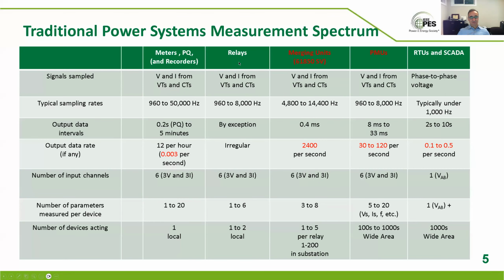Then we get to our more standard digital relays and meters. They sample at the rate internally they need. In a way, they are the front end of a merging unit, if you like. Relays don't send the measurements out often, only by exception. They send decisions out often enough. And meters typically, again, don't send waveform measurements. They send power and energy measurements, maybe every 5 minutes for some smart meters, things of that kind.